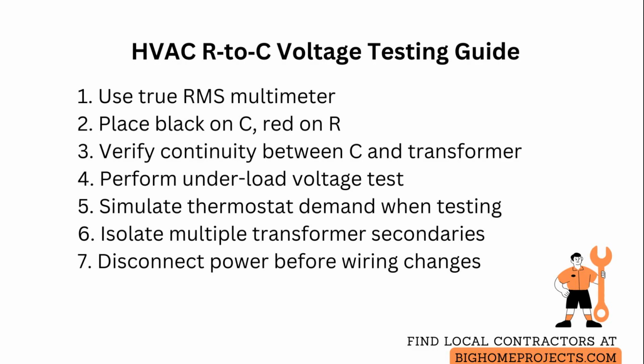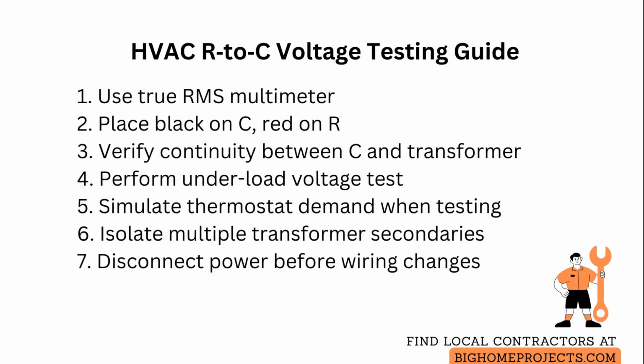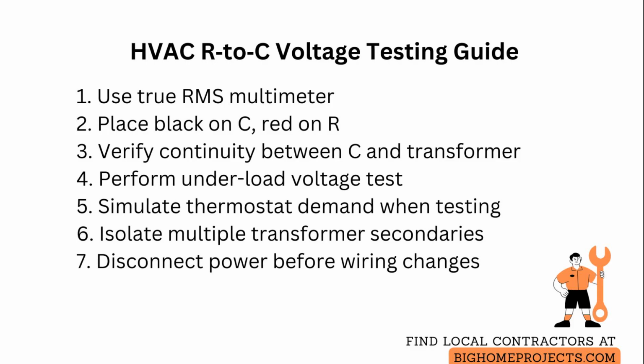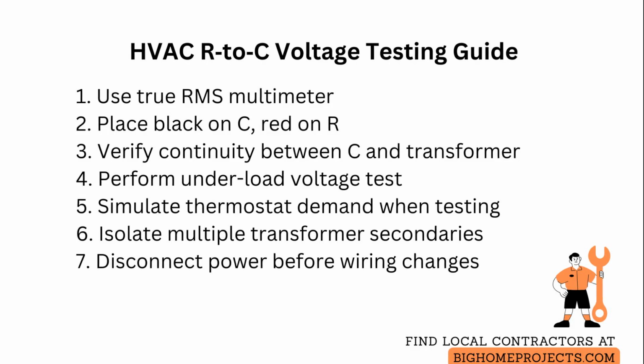If the system uses a separate common screw labeled C that is part of the furnace control board, verify continuity between that screw and the transformer's secondary common to ensure there is no open connection causing a false 0-volt reading.